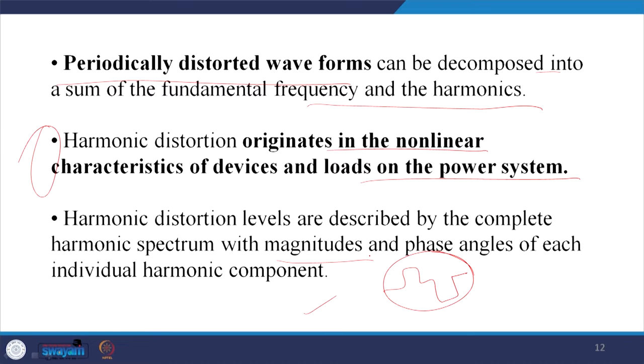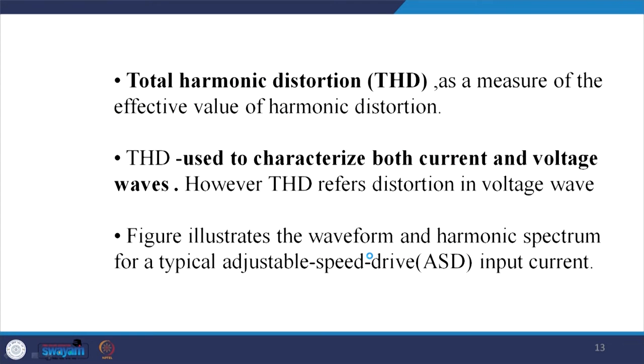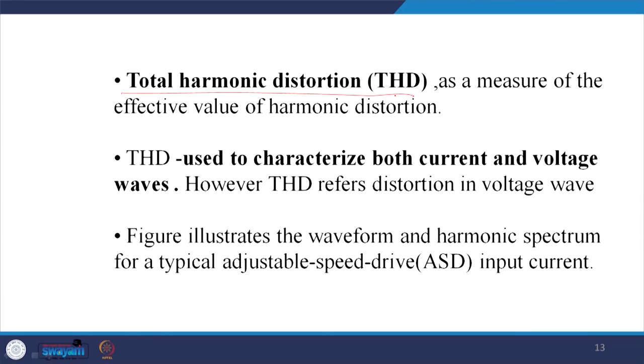Harmonic distortion levels are described by the complete harmonic spectrum, with the magnitude and phase angle of each individual harmonic component. Total harmonic distortion — THD — is a measure of the effective value of the harmonic distortion and is one of the prime criteria in power quality. It is used to characterize both current and voltage waves; however, THD sometimes specifically refers to distortion of the voltage wave.